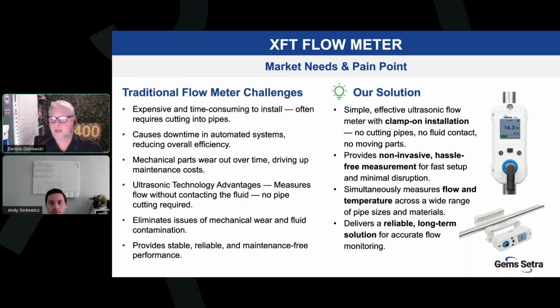The Clamp-On ultrasonic flow meter mitigates many of those problems, right? You've got clamp-on outside of the pipe, no contact, so you don't have to worry about contamination. You don't have to worry about corrosion. You don't have to worry about those pressure drops. So very simple installation, clamp it onto the pipe and read your flow and temperature from outside of the media. Next slide.